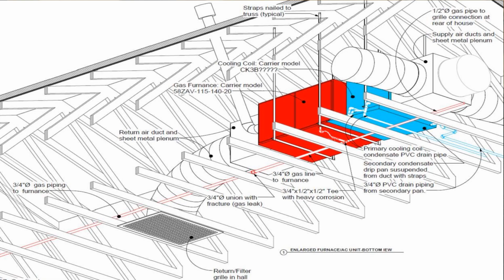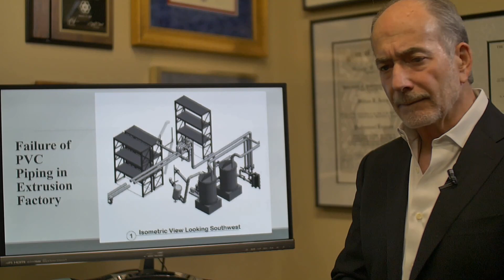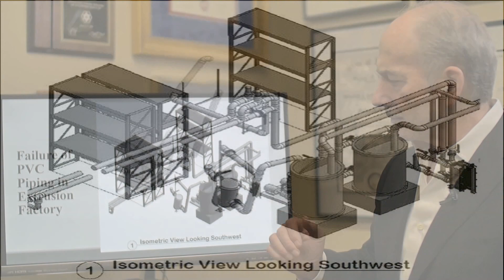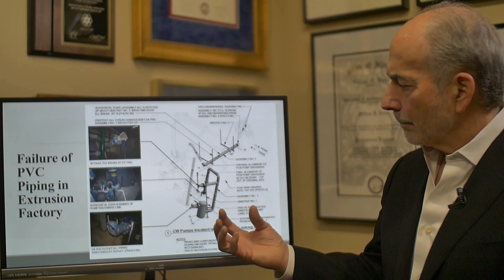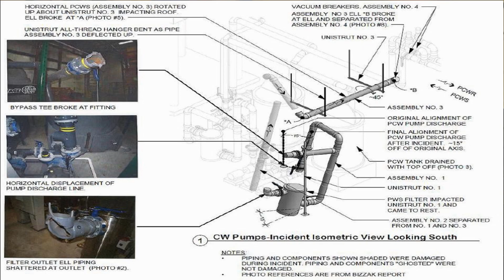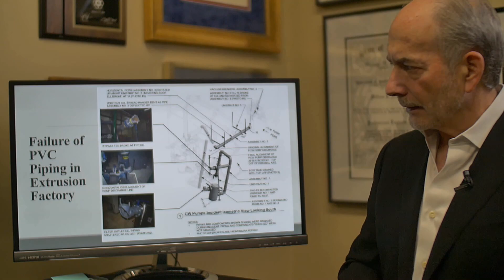The following project involves a rather unique situation involving large PVC piping in a manufacturing plant that failed in a very strange way due to water hammer. You've probably experienced water hammer in your home. If you shut off a valve too quickly, you can get a vibration in the piping. Well, when you shut off a valve too quickly in very large piping, especially brittle PVC piping, it can cause catastrophic failure of the piping. What we found was that the piping components and the filters and strainers weren't properly constrained, which allowed the pipe to deflect, broke the pipe, and injured a man quite severely.